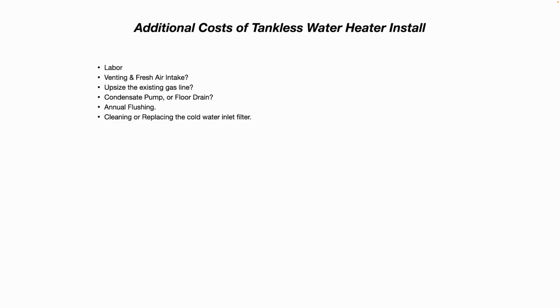You may have to upsize your existing gas line because the tankless water heaters run at a much higher BTU rating than the standard tank type water heaters do. So to get the proper amount of gas flow, volume of gas, you're going to need to generally upsize that gas pipe. So that's additional cost.